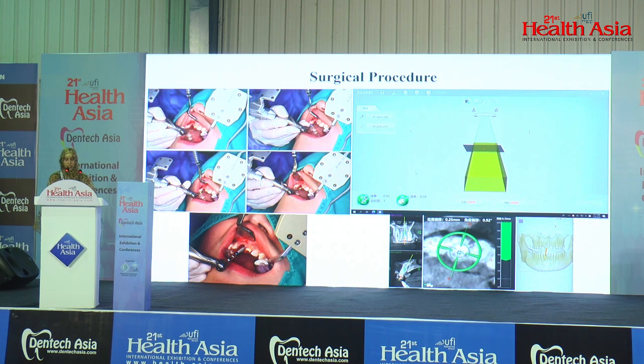As you can see in this screen, this is the planning software. You need to position yourself in the center. Once you deviate in any direction, mesial, distal, buccolingual, this circle will turn red, and then it will direct you that you are moving in a wrong direction, come to the center. So your position, your angulation, everything is guided, and this bar shows the length of the implant. From 0 millimeters up to the length, if you are placing a 12 millimeter implant, it will direct you. Once you reach the desired length, it will turn red. You need to stop over there. So during the surgery entirely, you will be guided by this software.